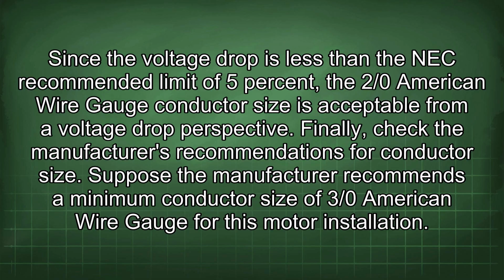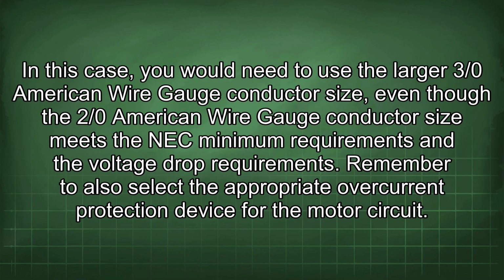Finally, check the manufacturer's recommendations for conductor size. Suppose the manufacturer recommends a minimum conductor size of 3/0 American wire gauge for this motor installation. In this case, you would need to use the larger 3/0 American wire gauge conductor size, even though the 2/0 American wire gauge conductor size meets the NEC minimum requirements and the voltage drop requirements.